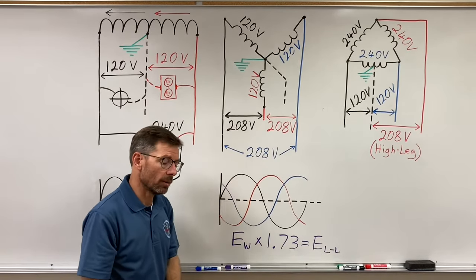On a balanced load — same voltage, same current down each branch — if you take any vertical point on the three-phase waveform and add the values, you should get zero. Any vertical point should add up to zero. That's the 120/208 three-phase Y or star system.